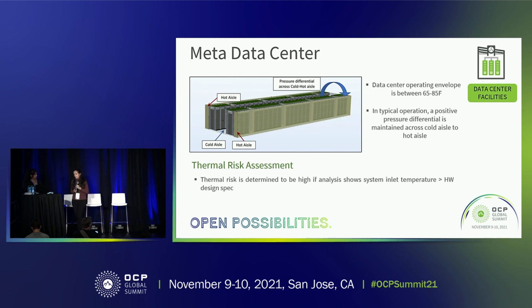A few more details about the data centers. Our supply airflow envelope is between 65 and 85 Fahrenheit. Also, we maintain a positive pressure differential between the cold and the hot aisle to prevent or minimize any bypass from the hot aisle to the cold aisle. When we do all of these different evaluations, both from a CFD perspective as well as the experimentation, our main goal is thermal risk assessment. And in this case, we determine the thermal risk is high if we ever see that the inlet temperatures for our IT equipment are greater than the hardware design spec that we have.